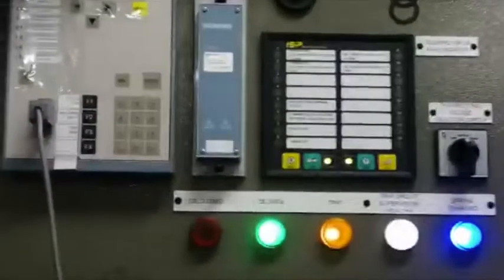This is our transformer SLD. Our LV side is 11 kV delta connection, 132 kV star connection. For testing differential protection, I just communicated these two relays. I initialized that relay as 132 kV. This one is 11 kV. Both relays are communicated through FO cable. Both are communicated.